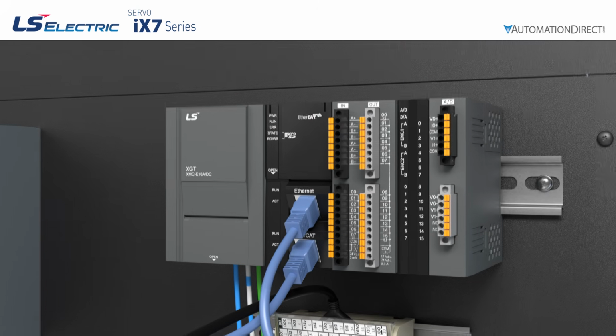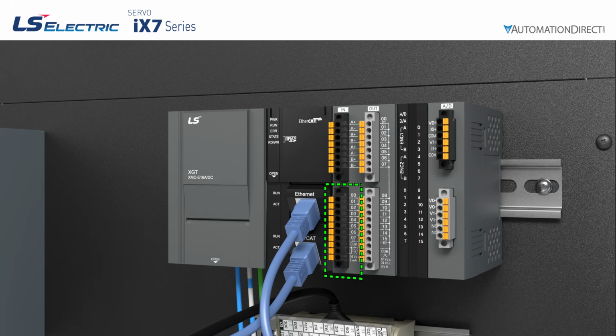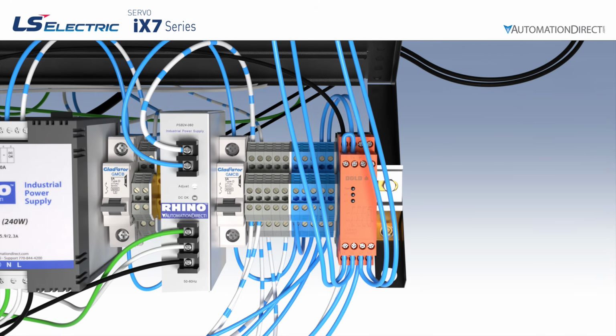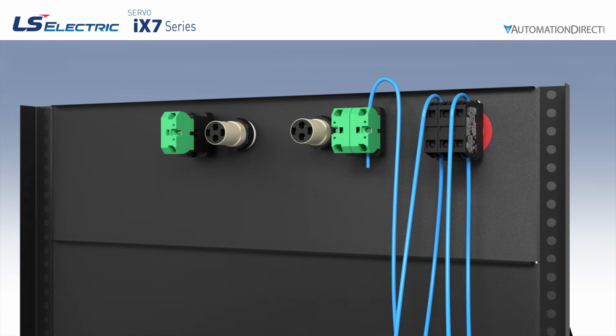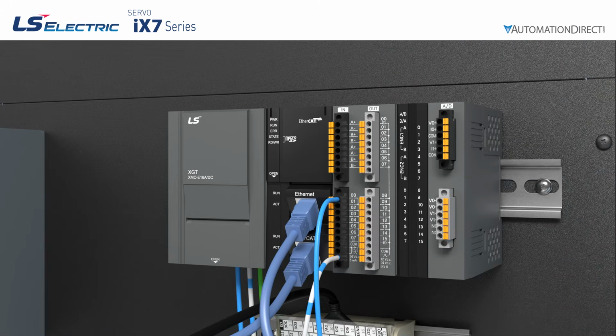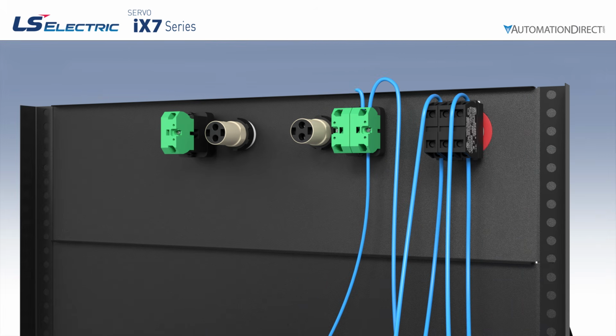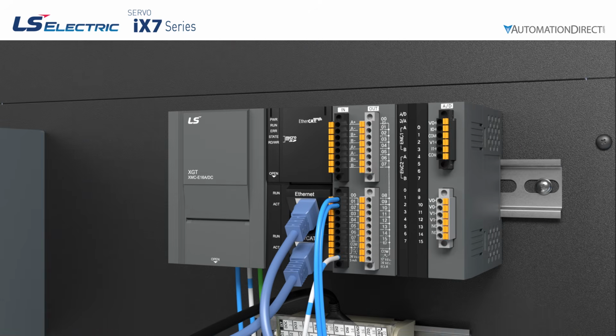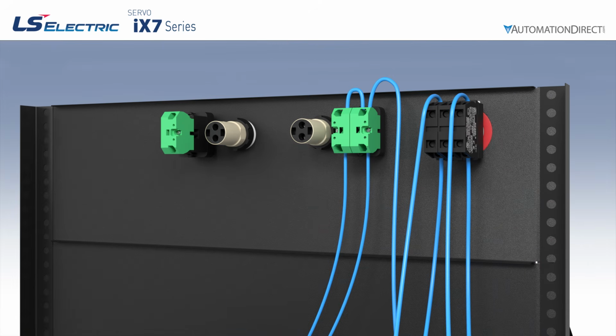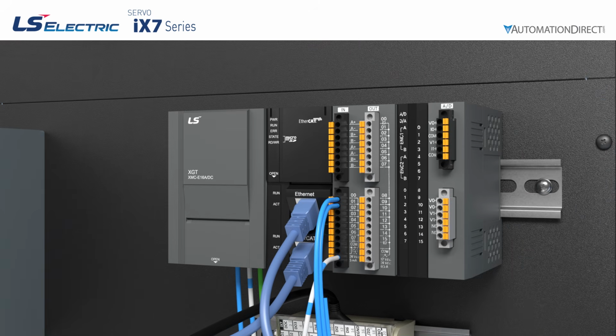For the XMC controller, digital inputs can be wired as either sinking or sourcing. In this design, we're using sinking inputs. The I/O supply's 0-volt common is connected to the controller's digital input common. DI1 is wired from plus 24 volt through the left selector switch contact to the DI1 terminal. DI2 is wired from plus 24 volt through the right selector switch contact to the DI2 terminal. DI3 is wired from plus 24 volt through the green push button contact to the DI3 terminal.